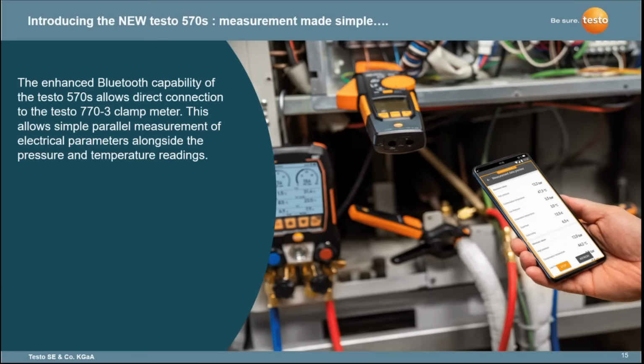One of the other aspects of the 570s is we've enhanced the Bluetooth capability so that it will allow direct connection to our testo 770-3 clamp meter. So this also now allows very simple parallel measurement of electrical parameters alongside your pressure and temperature readings. So a typical application here would be something like compressor current, and being able to measure the compressor current as well as the pressure and temperatures and see how the relationship is working, or whether it's actually a compressor fault that is causing the issues.